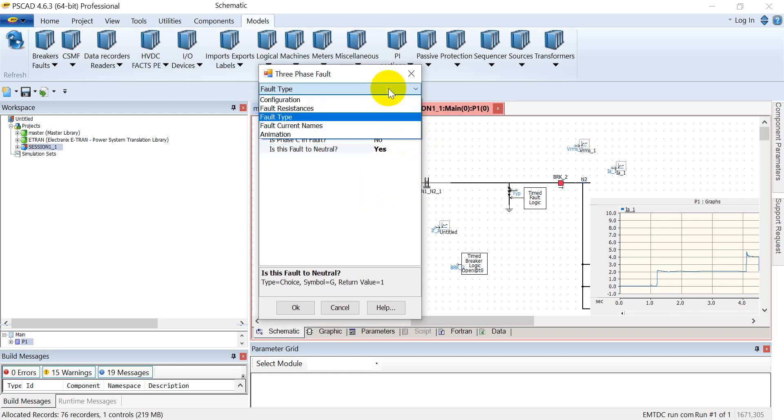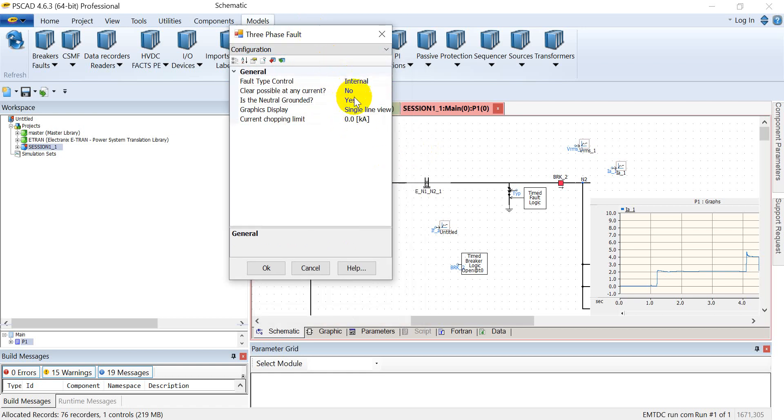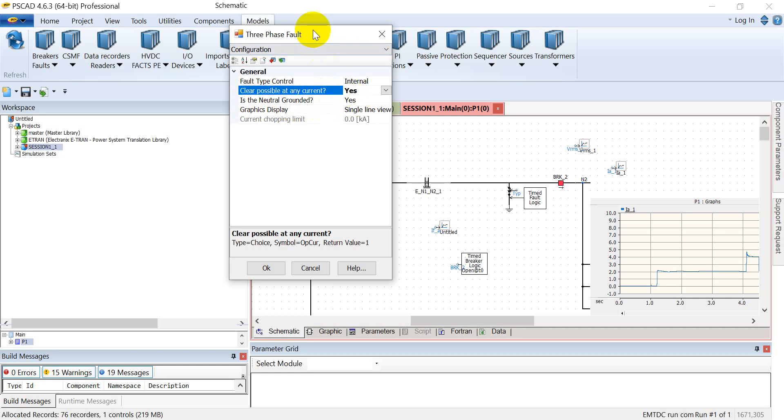Let's get back to the configuration. The other option is clear possible at any current. If I select it as no, then it will wait for the next zero crossing before clearing the fault. If I select it as yes, then it will instantaneously clear the fault.